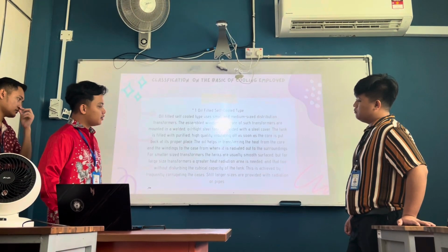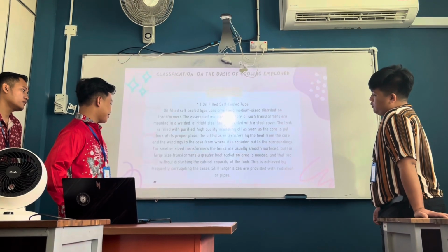For small size transformers, the tanks are usually smooth surface, but for large size transformers, a greater heat radiation area is needed, and that too without increasing the total capacity of the tank. This is achieved by frequently corrugating the case. Still larger sizes are provided with radiation tubes.